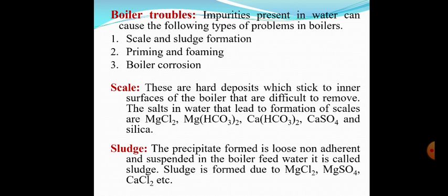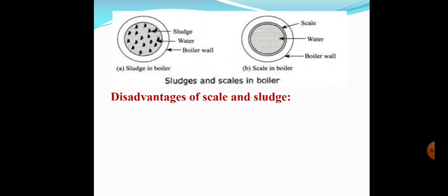Sludge is a precipitate that is loose, non-adherent, and suspended in the boiler feed water. Once sludge is formed, it gets collected at the cooler regions of the boiler and does not adhere firmly to the walls of the boiler metal. Sludge is usually formed due to magnesium chloride, magnesium sulfate, calcium chloride, etc. Here I have shown the figure of scale and sludge — sludge is a loose precipitate whereas scale adheres to the inner surfaces of the boiler.